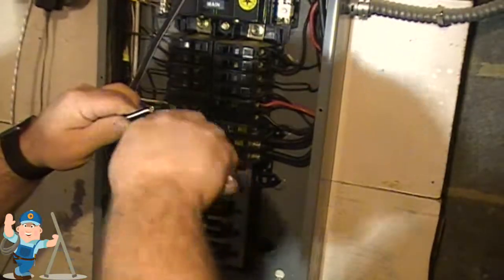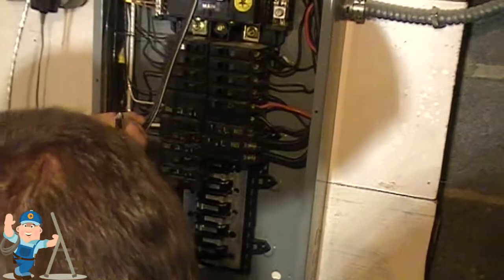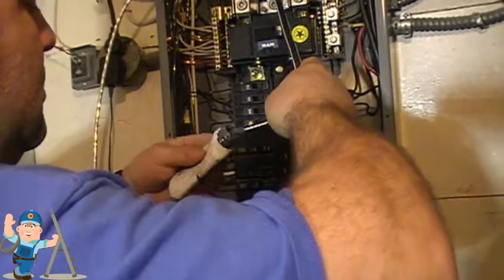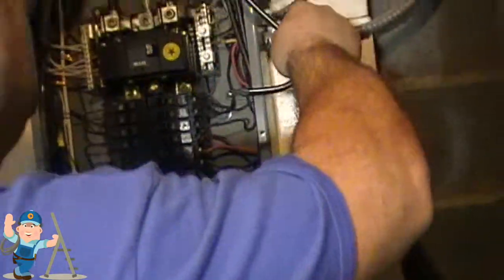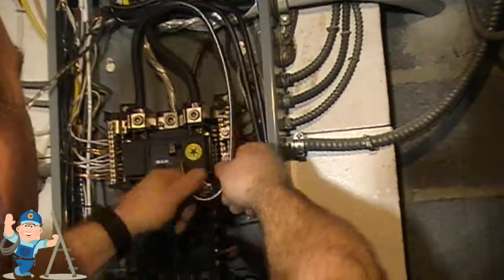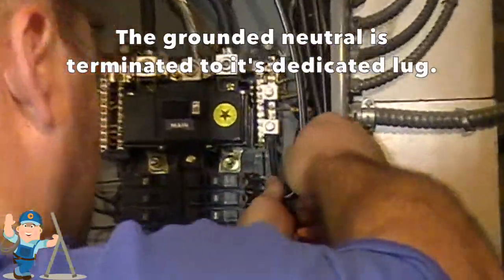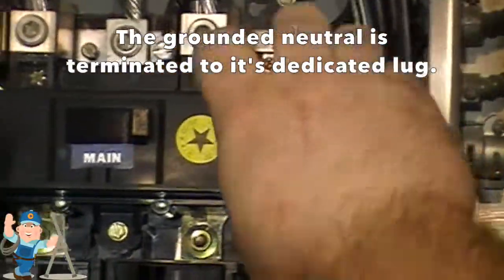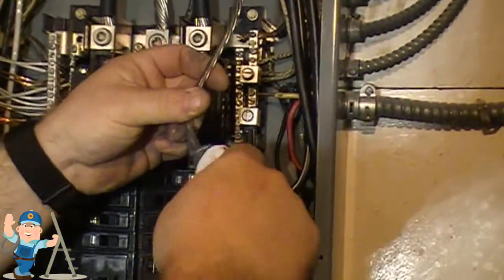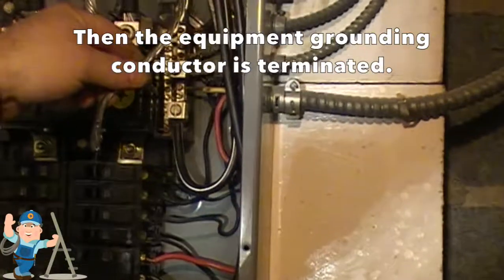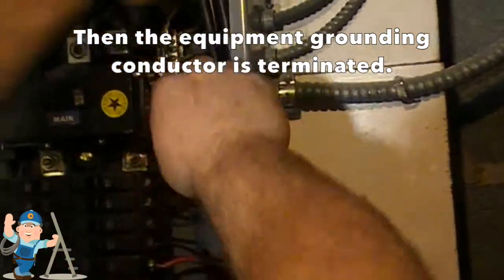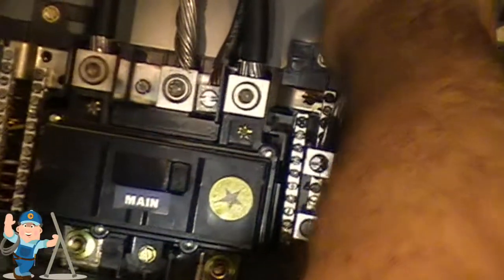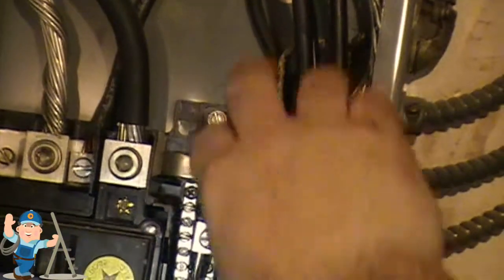So here I am cutting in the neutral, and of course in this QO panel, I'm guessing this is from the mid-80s sometime, the terminals that are built into the panel when you buy it are not large enough to add a sub panel. So you can see there on the right on that bus, I've added 2 new lugs properly sized for these conductors, specifically for the number 2 aluminum neutral, and most likely a number 4 aluminum equipment ground. Anyhow, so there we are, terminating them properly, and there you see them sit just right and properly terminated.